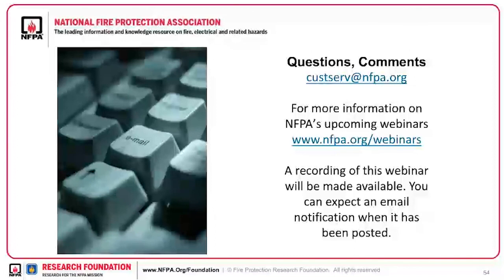Tom, maybe you want to handle this next one. Is off-gas detection of any value in early warning? I've heard that HVAC air velocities may affect the readings. So I don't have any specific data about the HVAC air velocities. Obviously, air velocity could affect any kind of gas sampling process that was going on. I'm not familiar with any research out there, but it is an area that could be examined as another means of trying to get to an early warning system.